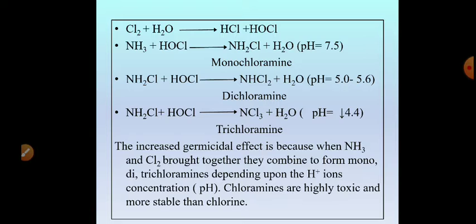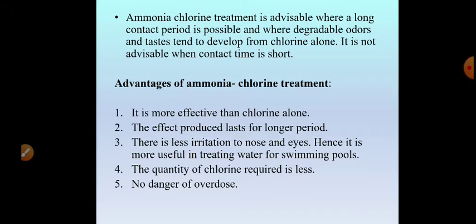Chloramines are highly toxic to microbes and more stable than chlorine. So, ammonia chlorine treatment is more effective as compared to chlorine alone. But we have to remember that ammonia chlorine treatment is advisable when a long contact period is possible, and where disagreeable odor and taste tend to develop from chlorine alone.